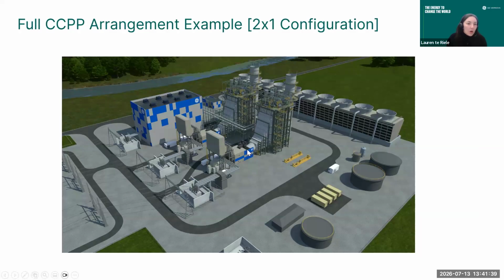As we saw before, you can put together the same picture: air comes in through these giant filters, the gas turbine, then our boiler or HRSG, and then the stack, where the exhaust gas goes out the top. In the previous view, everything was on one line, but in this configuration, the steam turbine is over here to our left. These two skids actually share one big steam turbine unit in this box.